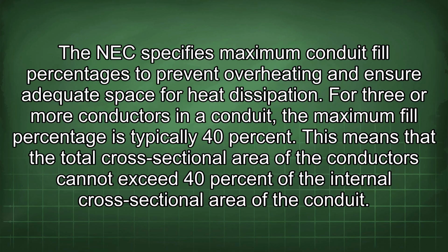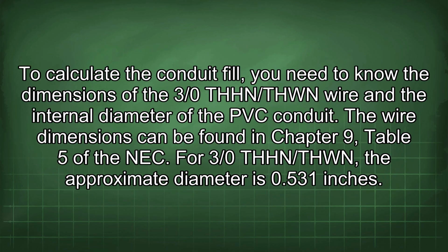The NEC specifies maximum conduit fill percentages to prevent overheating and ensure adequate space for heat dissipation. For 3 or more conductors in a conduit, the maximum fill percentage is typically 40%. This means that the total cross-sectional area of the conductors cannot exceed 40% of the internal cross-sectional area of the conduit. To calculate the conduit fill, you need to know the dimensions of the 3/0 THHN/THWN wire and the internal diameter of the PVC conduit. The wire dimensions can be found in Chapter 9, Table 5 of the NEC.